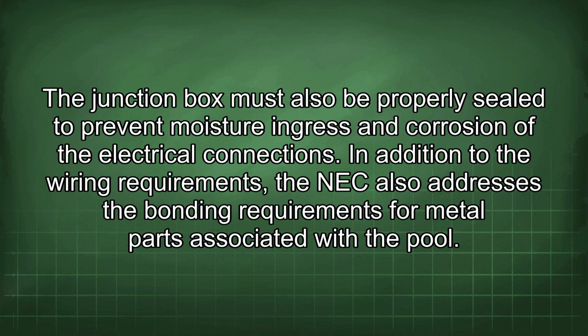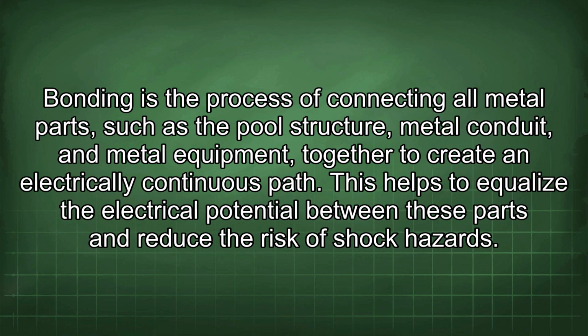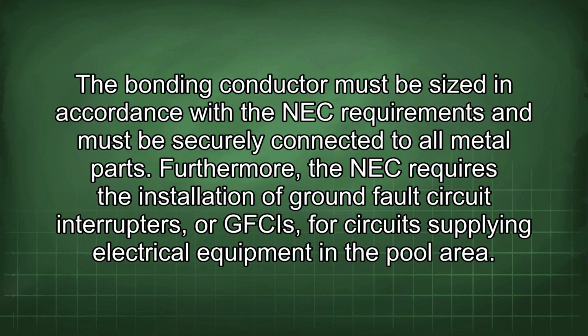In addition to the wiring requirements, the NEC also addresses the bonding requirements for metal parts associated with the pool. Bonding is the process of connecting all metal parts, such as the pool structure, metal conduit, and metal equipment together to create an electrically continuous path. This helps to equalize the electrical potential between these parts and reduce the risk of shock hazards. The bonding conductor must be sized in accordance with the NEC requirements and must be securely connected to all metal parts. Furthermore, the NEC requires the installation of ground fault circuit interrupters, or GFCIs, for circuits supplying electrical equipment in the pool area.